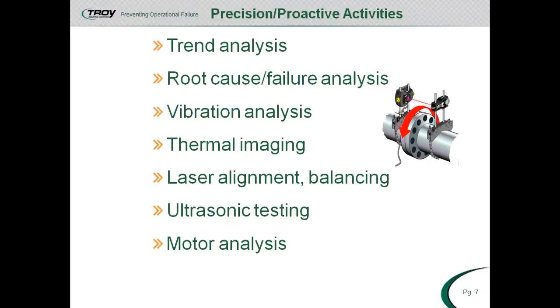All right, so motor analysis is one of our new activities. It's also known as PDMA testing. Motor analysis utilizes software and hardware to look at 6 fault zones in and around a motor's electrical circuit. The instrument can be applied to the output of a drive or a switch system going to a motor, and it can test everything, the entire electrical path.